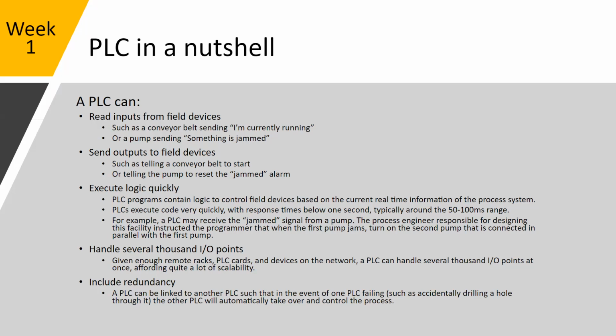PLCs, again, they can read inputs from the field. So whether that's, for this example, such as a conveyor belt sending, I'm currently running, or a pump sending a fault. Something is jammed. They'll send outputs telling the conveyor belt to start, telling the pump to reset, whether that's a VFD or whether that's an overload, to try to get the system, whether that's inputs to a motor starter, to run.